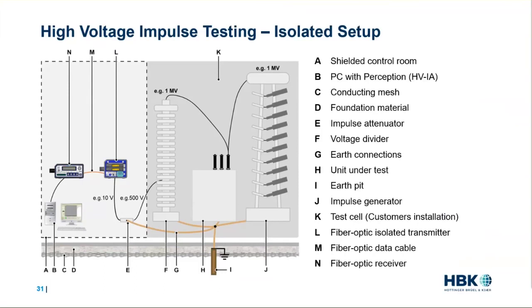So in this example, the advantages that you gain compared to a traditional test setup include there's no electrical connection between the test cell signals and the measurement equipment and the PC powered in the control room. So this creates a safe environment for both you, the user, and the equipment. There's also no equalizing currents between the test cell earth connection and the mains earth connection. Also, placing the impulse attenuator and the battery operated digitizer in the shielded control room means a minimum exposure to electromagnetic disturbances.